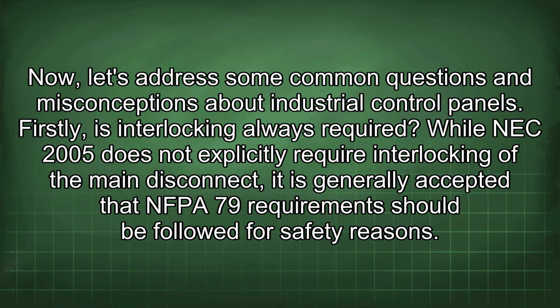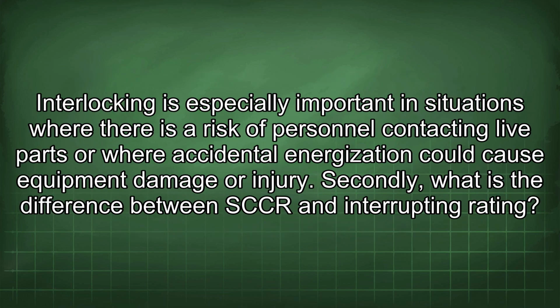Firstly, is interlocking always required? While NEC 2005 does not explicitly require interlocking of the main disconnect, it is generally accepted that NFPA 79 requirements should be followed for safety reasons. Interlocking is especially important in situations where there is a risk of personnel contacting live parts or where accidental energization could cause equipment damage or injury.